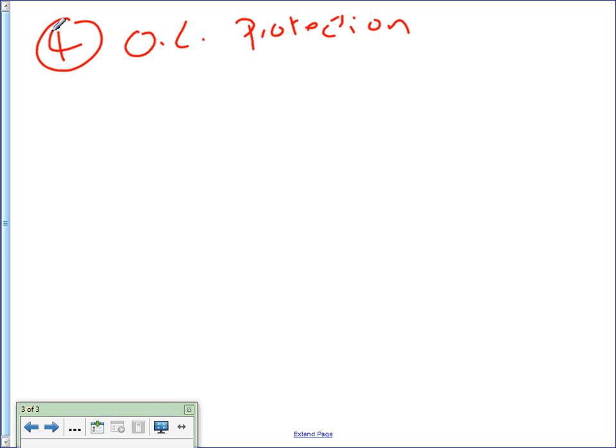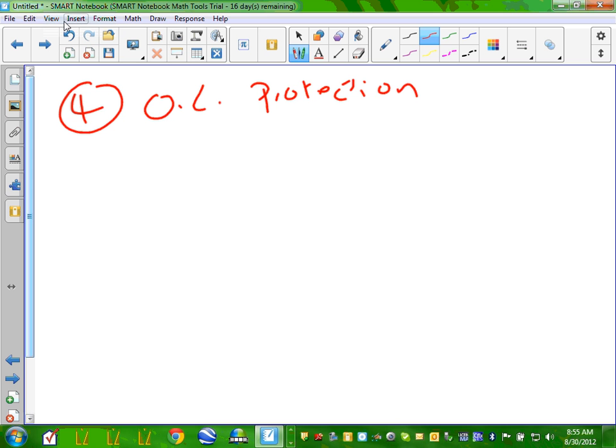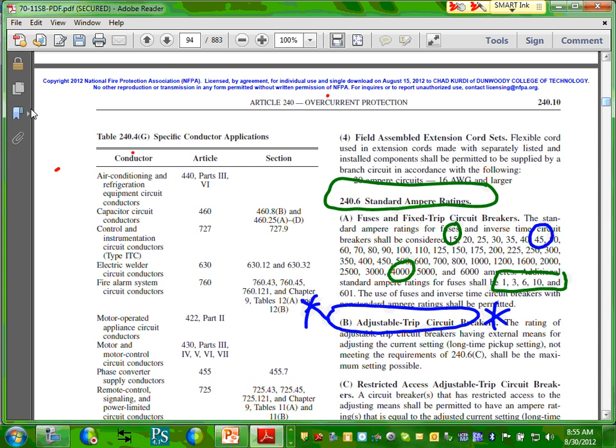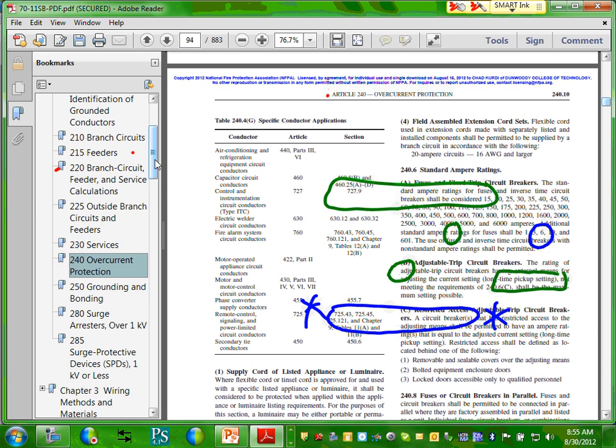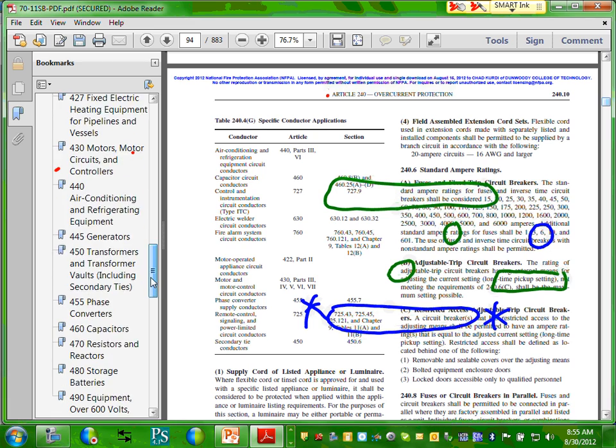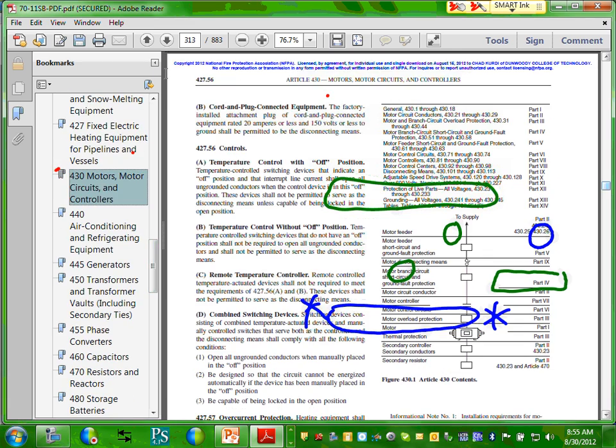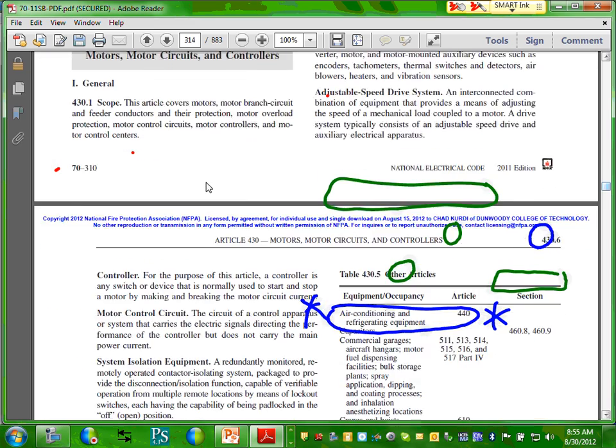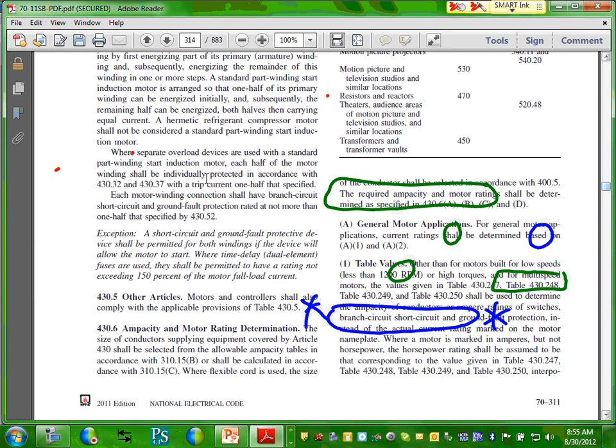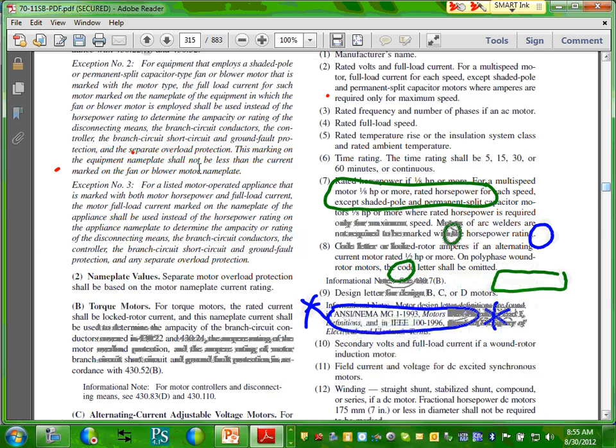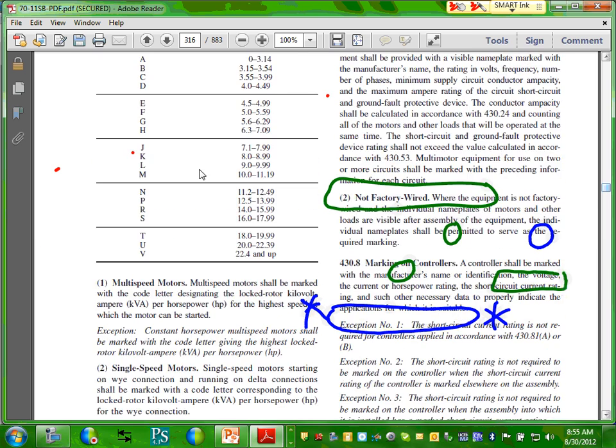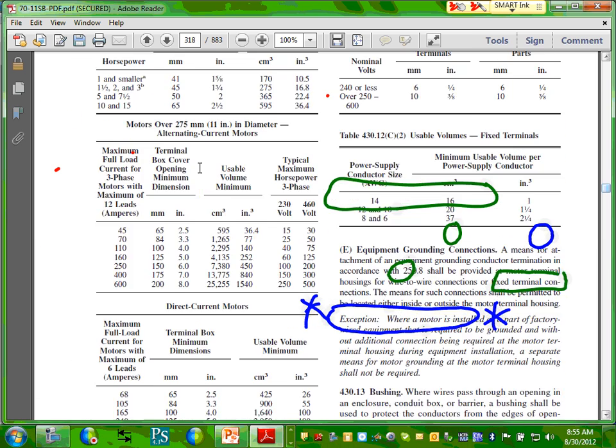Overload protection. For overload protection, guys, I'm going to flash my code again. And I want you guys to highlight this one back. The nice thing about electronics, back into my NEC code book. And we're going to go to 430. Where do we do the overload, Chad, again? 22, I think, 430 the overload. 430.32. Can you guys go to 430.32? 430.32 all the way.